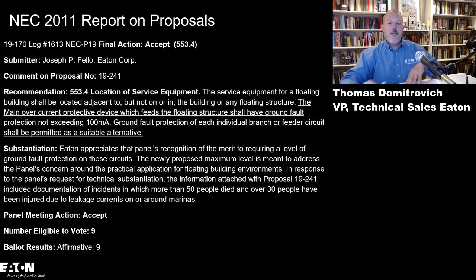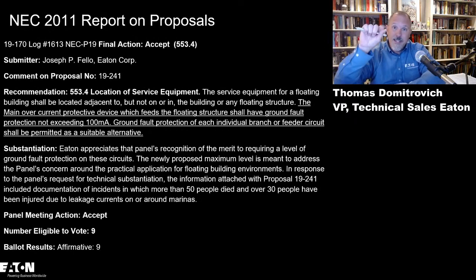So what Joe and I did, Joe Fello worked for Eaton. He's retired now. His job was to test. He was our UL guy, in our residential product line, and he focused on testing all of the GFCI circuit breakers. So he knew GFCIs and the UL standards associated with that. We tested and we grabbed every one of our manufacturers' products, and we found that from a ground fault protection of equipment perspective, if you understand UL 1053, and if you don't, we talked about this in our presentation on Monday with Nihad El-Sharif, that GFPE, the pickup point, is established by the manufacturer, or by the engineer or whoever it is that's setting the device in the field.